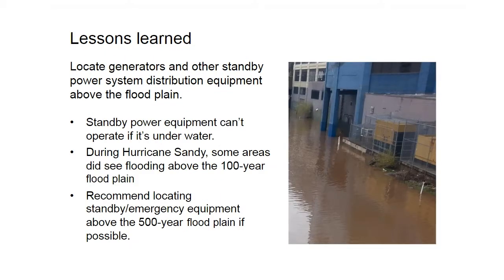So I know Scott and I both talked about some requirements, some of the lessons learned we've had over the last couple of events, like Sandy. We had some floods in the south, some floods out west. One of the lessons learned is just to make sure the equipment is above the floodplain. I mean, if it's underwater, it's not going to run. We did see with Hurricane Sandy and even some of the floods out west and in the south go over a 100-year flood. So we would even recommend going as close as you could to the 500-year floodplain to make sure you get that equipment up out of the water.